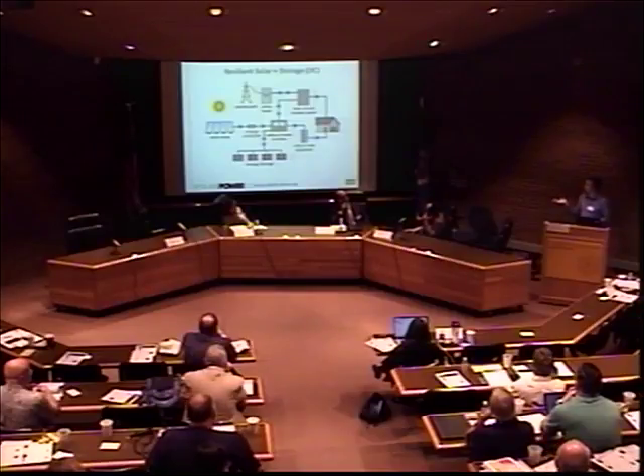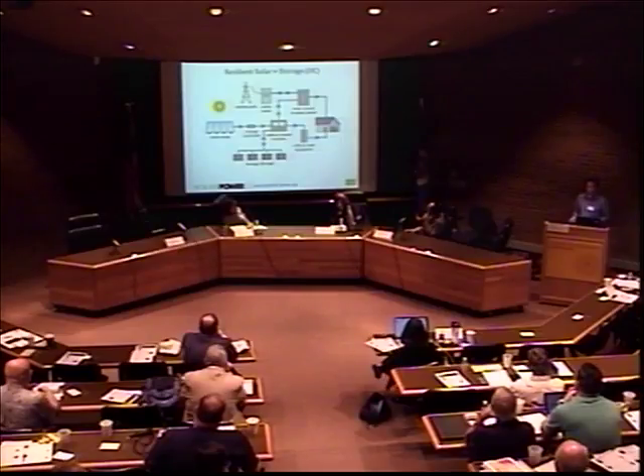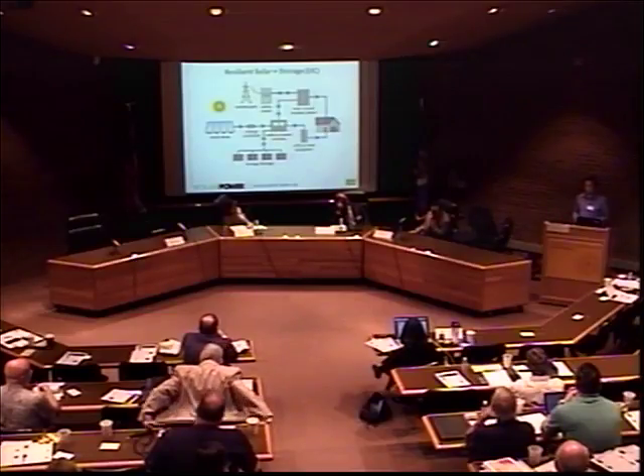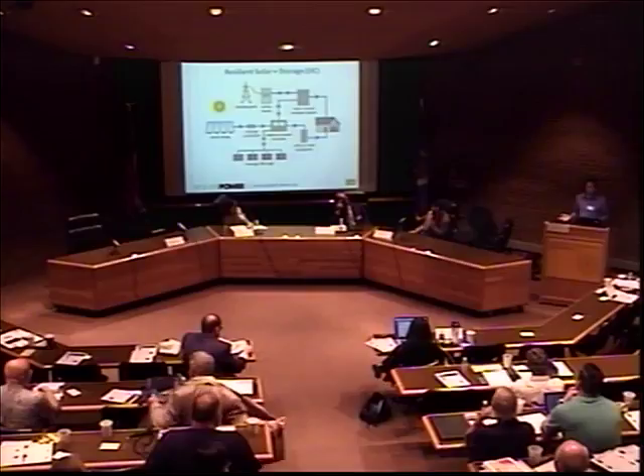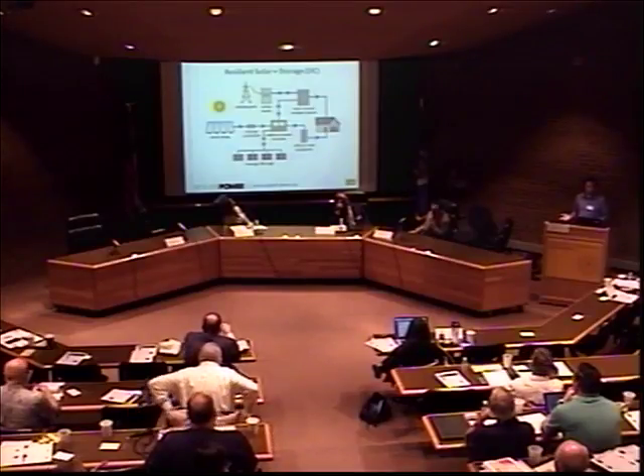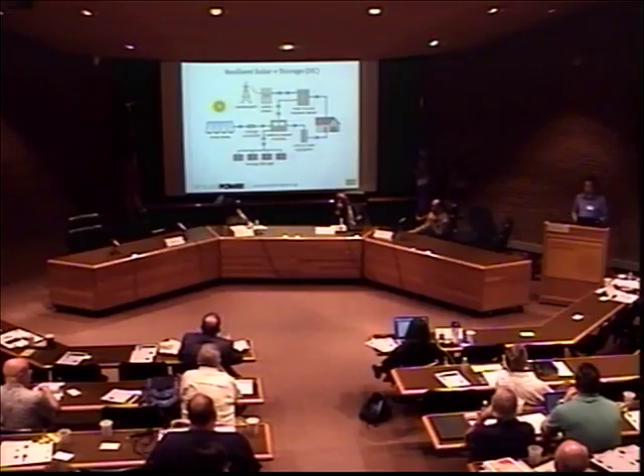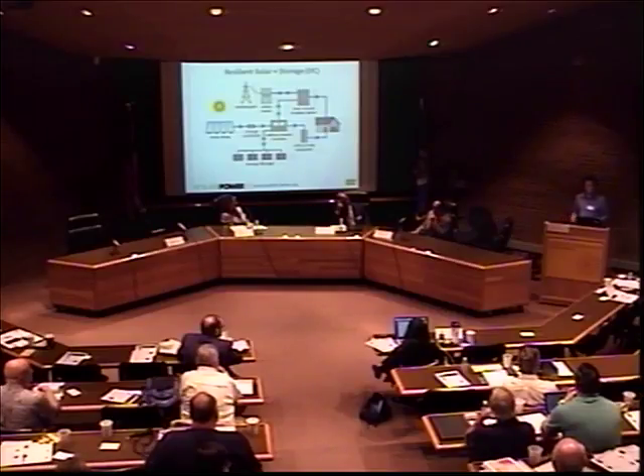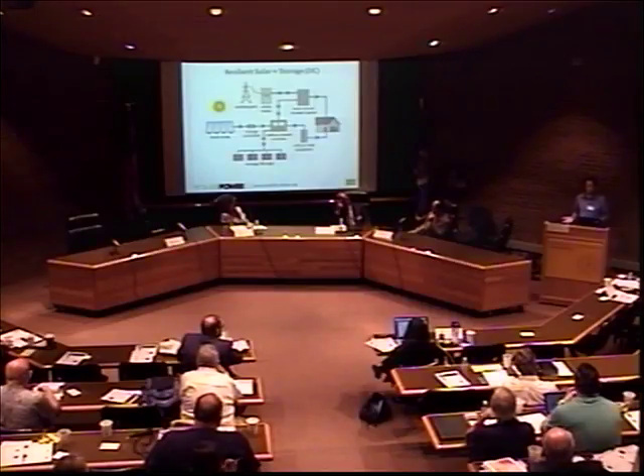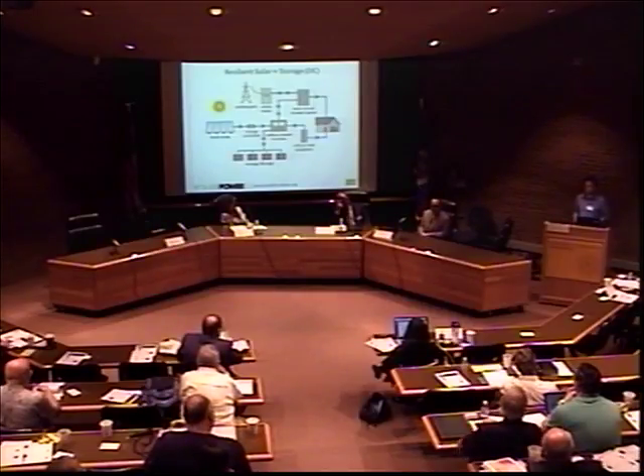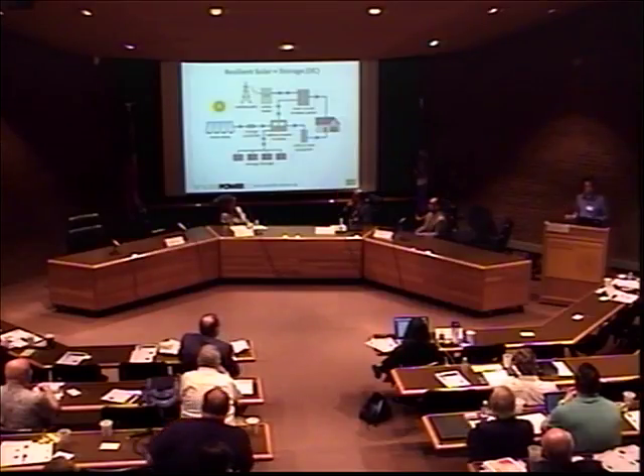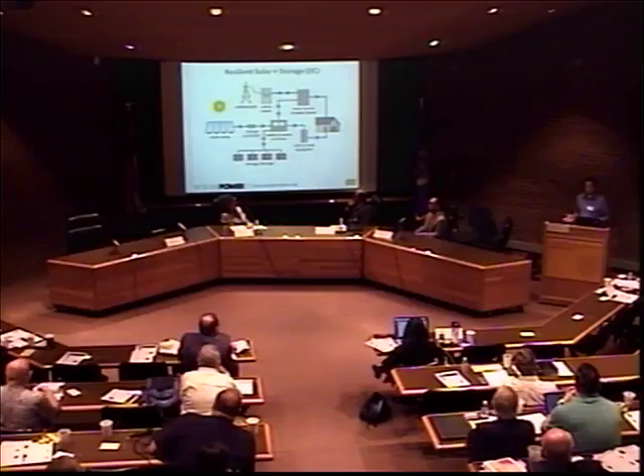Why do you need the critical load subpanel? Why can't you just put it all through the main circuit panel? Part of that is because of the limitations of energy storage at this time. It's not economically viable in most situations to power your whole facility with energy storage and solar, mainly because of the cost of batteries. We've heard before that batteries are not great with their power density, but they are much better with their energy density. So some of the high-powered technologies you're using, like motors starting up, energy storage may not be the best at supporting those loads. You might need other systems to go along with it.